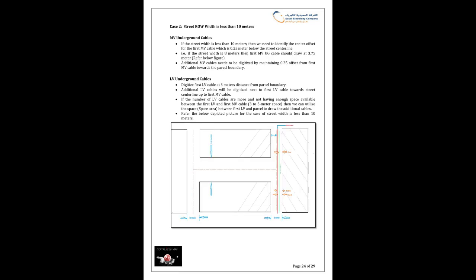Case 2. Street row width is less than 10 meters. MV underground cables. If the street width is less than 10 meters, then we need to identify the center offset for the first MV cable, which is 0.25 meter below the street center line. I.e., if the street width is 8 meters, then the first MV-UG cable should be drawn at 3.75 meters, refer to the figure below. Additional MV cables need to be digitized by maintaining a 0.25 offset from the first MV cable towards the parcel boundary.